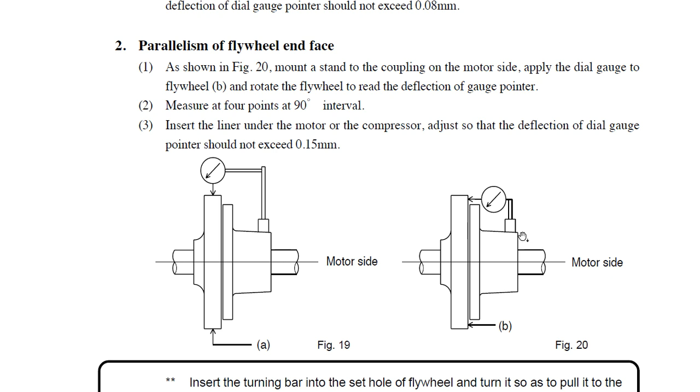In this figure, as you can see, we place the gauge on the motor side on this surface. The measurement is the same: four different points by 90-degree intervals. Insert the liner under the motor or the compressor and adjust so that the deflection of the dial gauge is within the limit. Here we have a different measure: 0.15 millimeters.